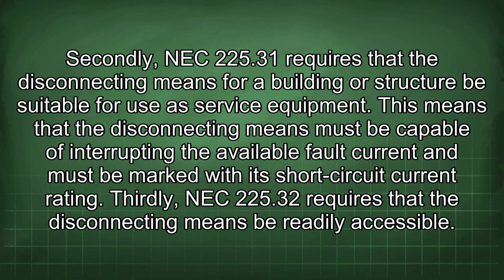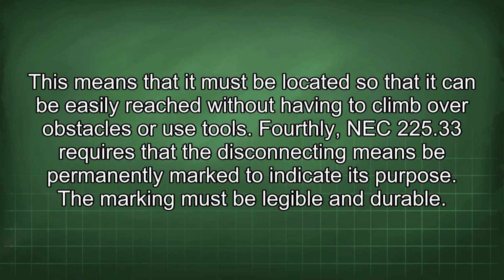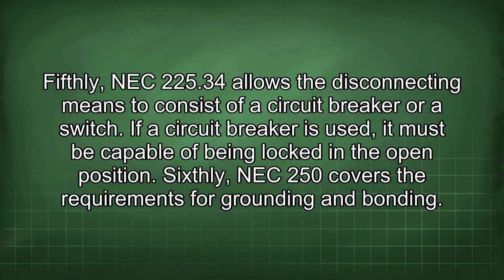Thirdly, NEC 225.32 requires that the disconnecting means be readily accessible. This means that it must be located so that it can be easily reached without having to climb over obstacles or use tools. Fourthly, NEC 225.33 requires that the disconnecting means be permanently marked to indicate its purpose. The marking must be legible and durable. Fifthly, NEC 225.34 allows the disconnecting means to consist of a circuit breaker or a switch. If a circuit breaker is used, it must be capable of being locked in the open position.